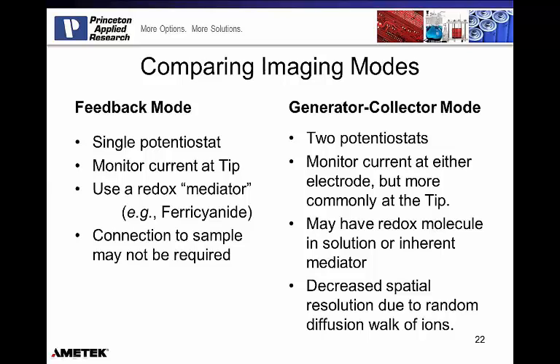So again, let's take a step back and compare the two modes. We're going to do feedback mode, which is going to be a single potentiostat. I'm going to just monitor current at the tip. I'm going to use a redox mediator such as ferrocyanide or Ru(NH3)6 or some other well-characterized reversible redox couple. And in this feedback mode, the sample connection may not be required. This is very nice from a sample mounting standpoint, you do not even need to make a wire connection to your sample if you're only going to be imaging in feedback mode. And this is really going to be used for approach curves, and for the ability to measure localized conductivity and make comments on that.